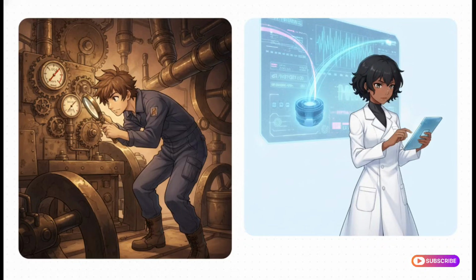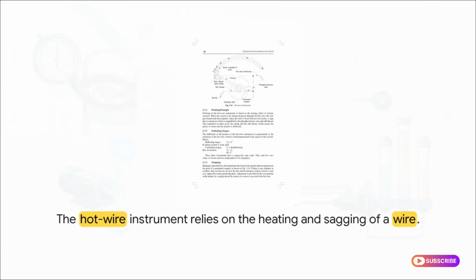It's basically the difference between checking your car's oil with a dipstick versus having a sensor just pop a notification right up on your dashboard screen. But it's funny, the very first electric pressure gauges and indicating elements were surprisingly physical themselves. Early electric indicating elements, like the hot wire instrument, actually relied on the heating and sagging of a wire, usually a superfine platinum wire. When electrical current from a sensor passed through it, the wire heated up, expanded, and physically sagged. That sag was pulled by a spring in a silk thread, causing a pulley to rotate a pointer. It was just a totally ingenious way to measure electrical quantity completely independent of the current's frequency.